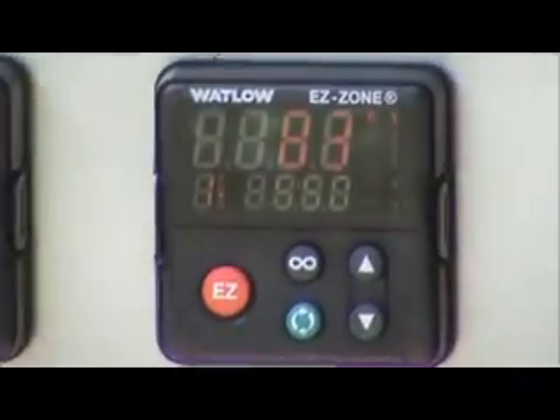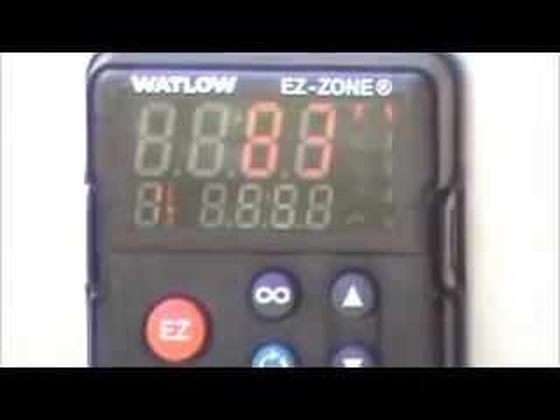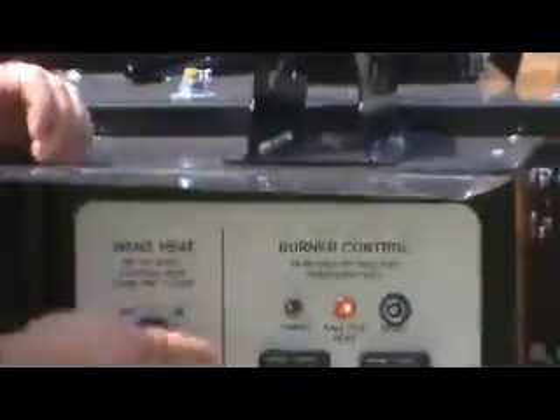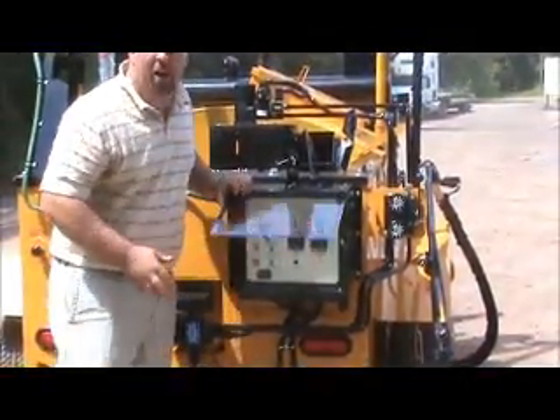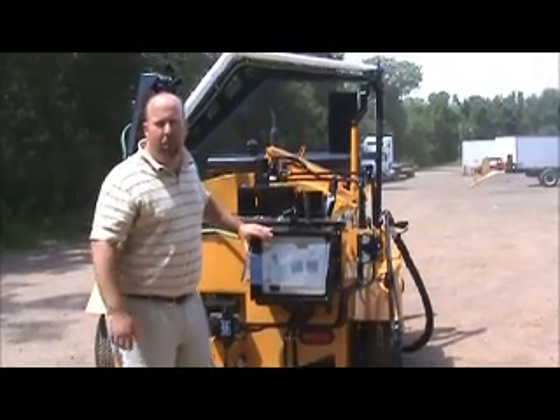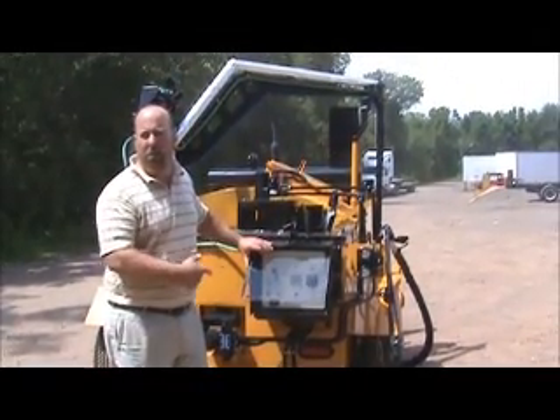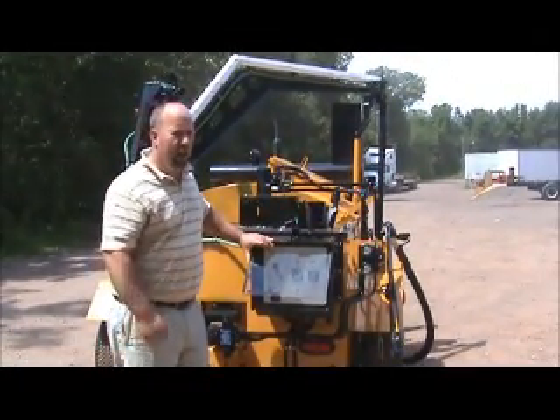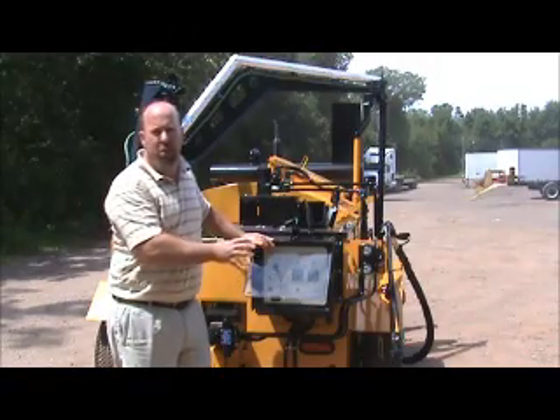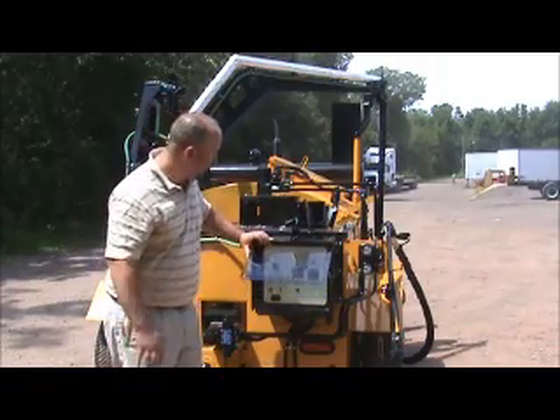Just let the burner do its thing. We're going to heat. So you'll notice that we have very little or no smoke coming out of the stack. Our call for heat light's on. That's our thermostats telling the burner to run. So that should be on when the thermostats need heat. If that light's out, the thermostats don't need heat, the burner should be off.